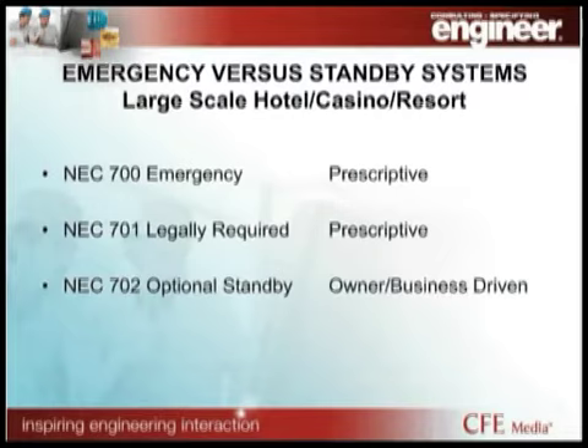So some of the things that you hear me talk about, if you've got questions on it, are based on our practice here, and also in Asia and other parts of the world where we do quite a bit of large-scale systems. When we talk about a large-scale system that's not a hospital environment, as Gerald covered, you take a look at NEC 700 for emergency, 701 for legally required, 702 for optional standby. Those are the primary codes that are going to drive us. 700 is very prescriptive. It's very limiting with respect to what you're allowed to put on the true emergency system. Legally required is also very prescriptive, and if you think about the purpose of those, which we'll talk about in a little bit, it's clear why they would be as prescriptive as they are.